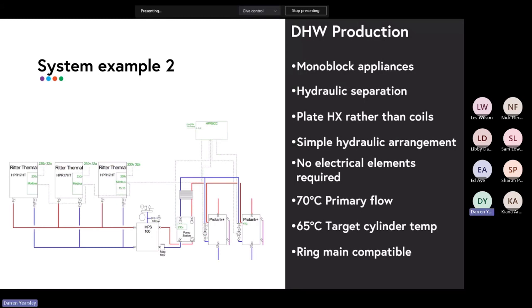Very simple hydraulic arrangement. So on the cylinders, you've just got a manifold cold in, manifold hot out. The cylinders are in parallel, so you're delivering all of the water at the same time through both tanks. No electrical element required. This particular system, we're flowing 70-degree primary flow, and then we're at 65-degree target temperature in the tank. And again, it's ring main compatible.